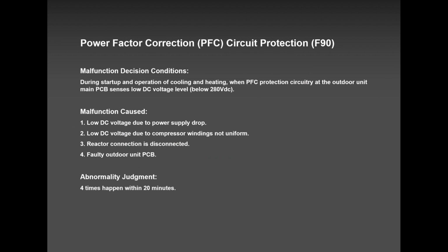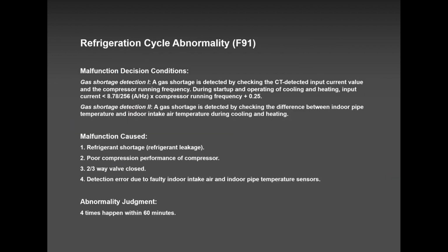F90, it's the outdoor PCB. But before you change the PCB or before you condemn the outdoor PCB, do a 15 to 20 minute power reset. Switch off the outdoor unit for 10 to 15, even 20 minutes is good, and try it. I bet you the unit will kick in. It happens sometimes, just like a computer bug. You need to reboot it.